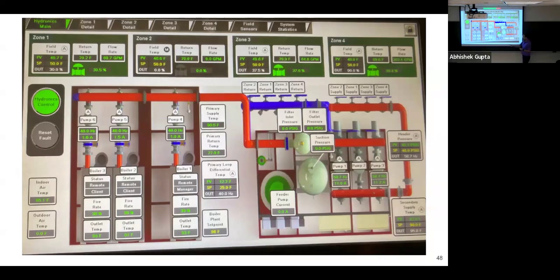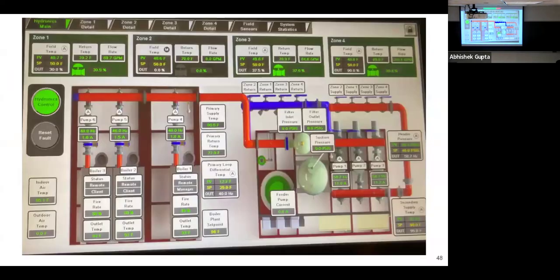The outside air temperature is failed at 0 degrees. A lot of the decisions made in the control system are based on the outside air temperature, so you can see that point is failed, it's reading zero. I think so, zero is the default value there? Well, I knew it wasn't 0 degrees outside. So it can be zero or it can be a fault, but it was cold, but it wasn't zero outside.